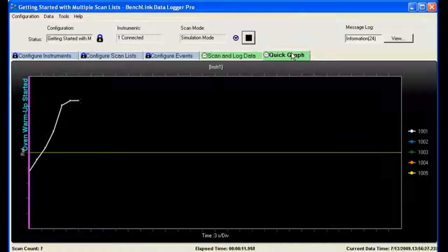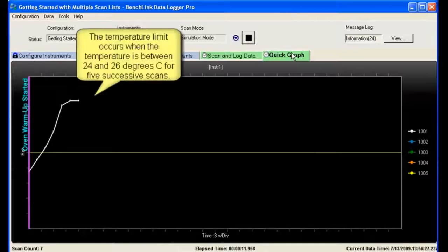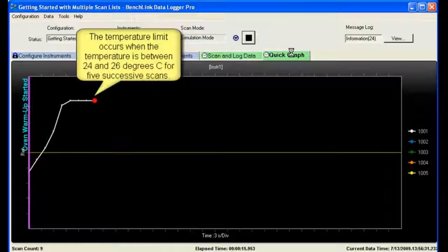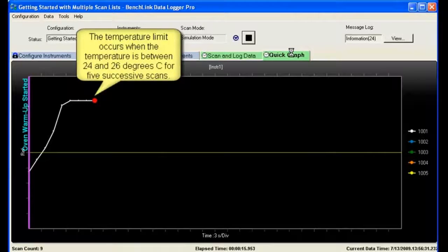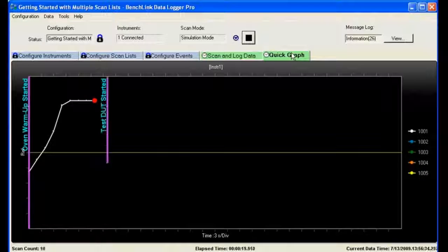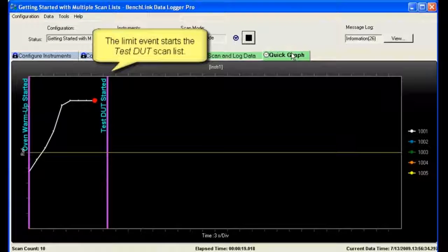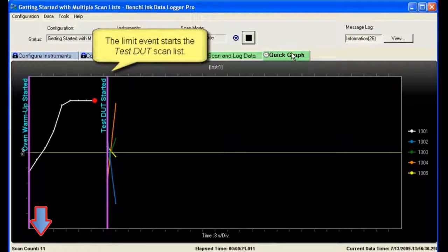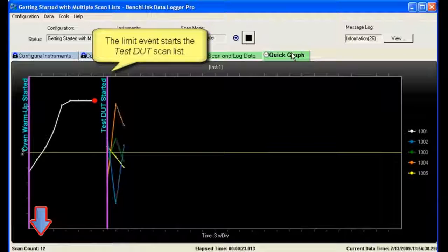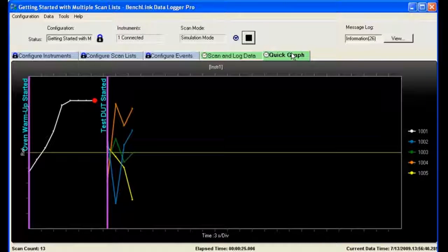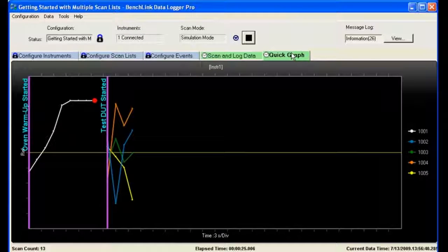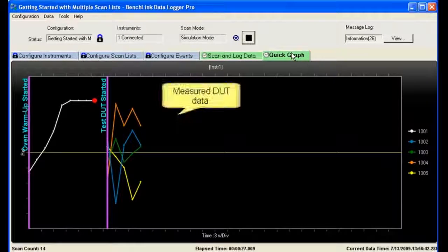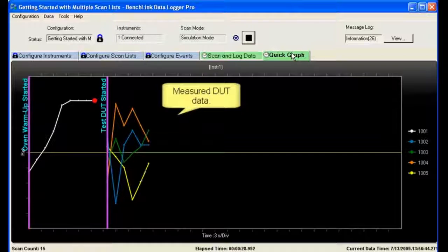It's starting to stabilize. So there's one, two, three, four, and five. So I've had five sequential readings that are within the limit. So we start counting on our scan where we're actually scanning data. Now this is going to go for eight scans.